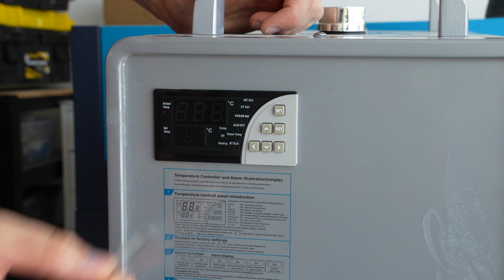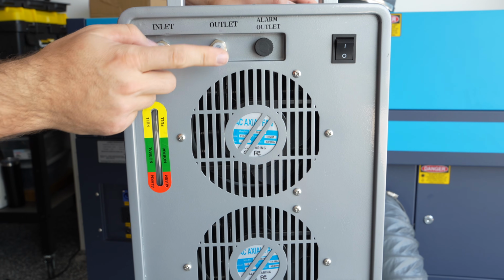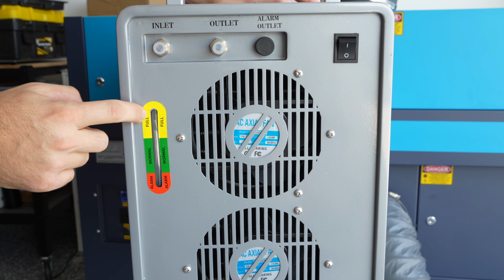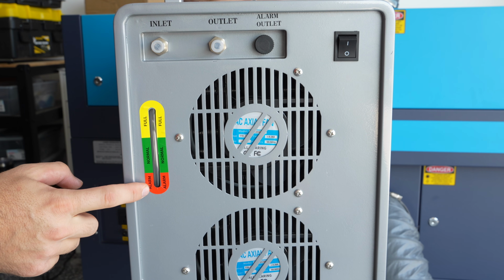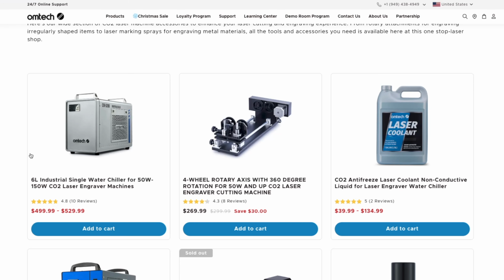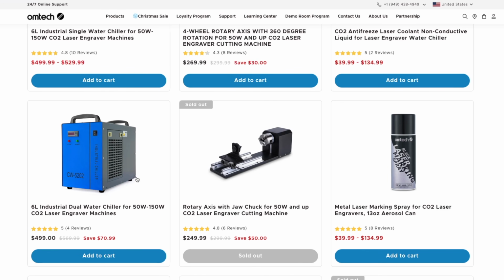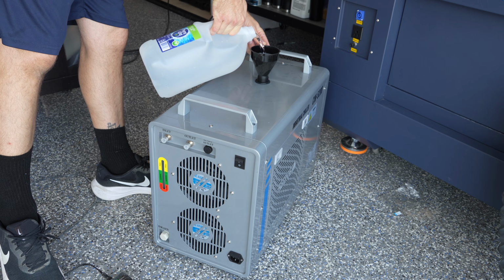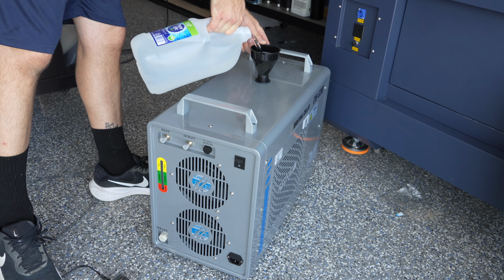There's also a built-in safety feature that connects the laser to the chiller with a cable so that the laser won't fire without the chiller operating. This is to prevent permanent damage to the tube caused by overheating. Omtech has two chiller options, but they're fairly similar in capacity, and the silver version that I got in seems to be the latest version.